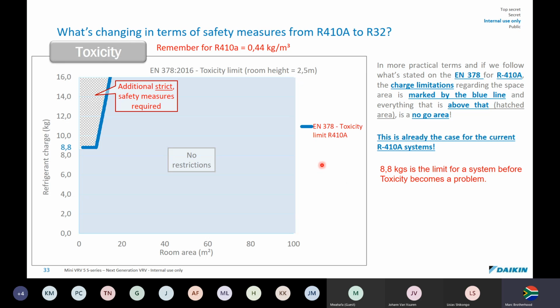If we look at this diagram, which can look a bit complicated, let's just look at the room area here. This isn't volume, this is just square meters. And we're talking, say, 410A here. And this is a roof height of, say, 2.5 meters. It's more practical if we follow what is stated in the standard EN 378 for 410, the charge limitations regarding the space area marked by the blue line. So this blue line here is what we use. So in a nutshell, if we use the EN 378 standard, 8.8 kilograms is the limit for a system before toxicity becomes a problem.